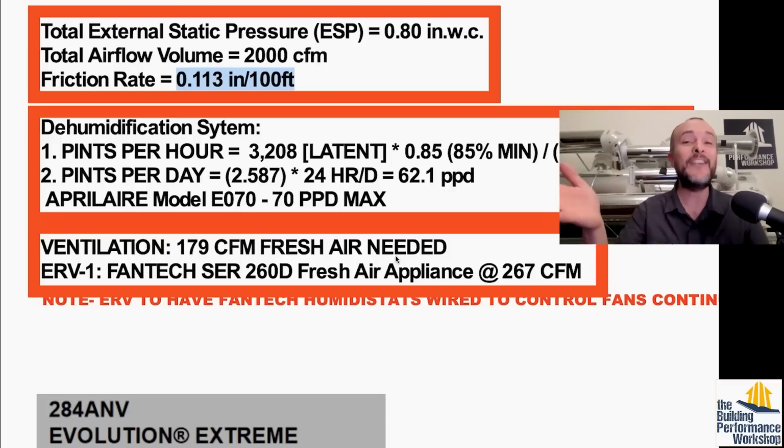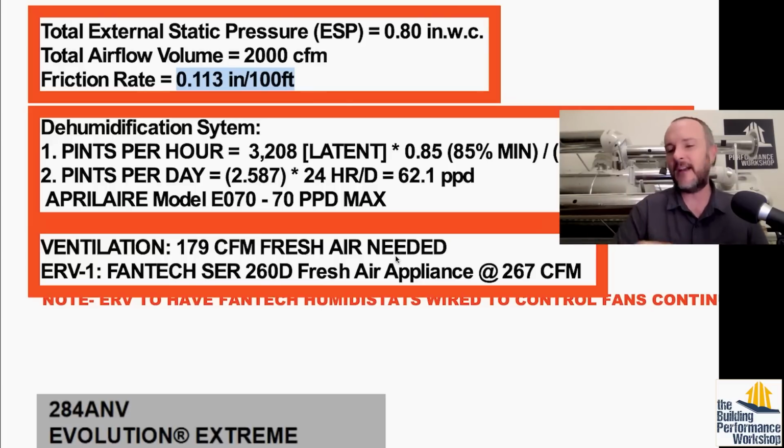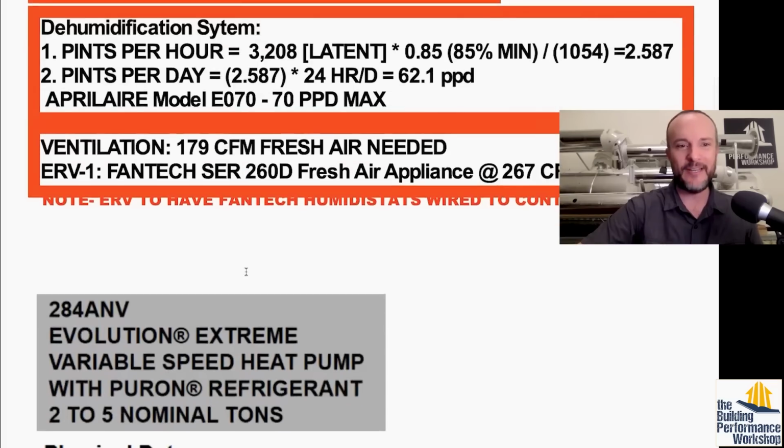And even with the exhaust count, which, you know, always we've got to figure out what the ASHRAE recommended ventilation is and then also count the exhaust, because we're going to use the ERV to exhaust from the bathrooms. Even that is 120. So we're way oversized, at least 50% oversized on this ventilation calculation. So that's, again, boosting the amount of load that this calculation is assuming we need, even if the Manual J was done with all the other inputs being correct, which it has not. So they're recommending a 260 CFM ERV, which is, again, more than double the size that you actually need.